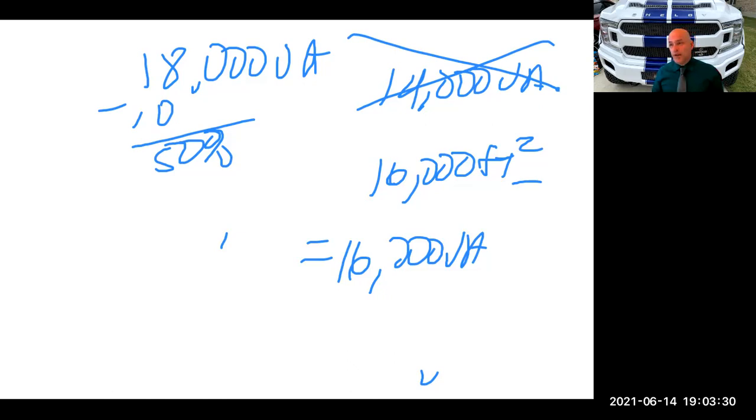And be careful if you're trying to figure one out and your answer comes very, very close to one row or the other. For example, let's say you were trying to calculate how many 750 kcmil conductors you can fit in an EMT. If you look at chapter 9, table 4, EMT, there was a question where the way they set it up was kind of impressive, if you ask me. It was actually a rigid conduit, if I'm not mistaken. But either way, for EMT, if you look at 3.5 inch under the 40% fill, you have a value of 4.618, right? So they gave these 4 750 kcmil conductors some kind of insulation, and when you did the math, it came out to be 4.678 or something like that.